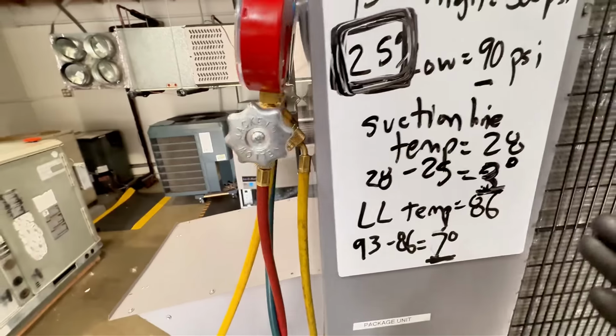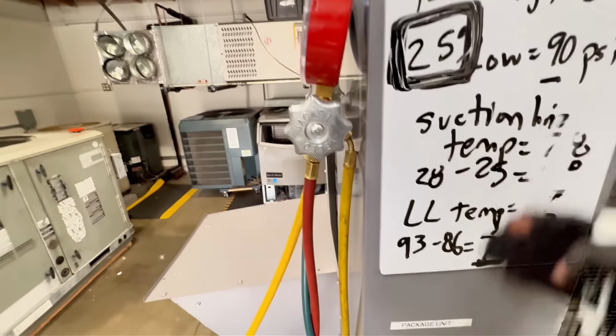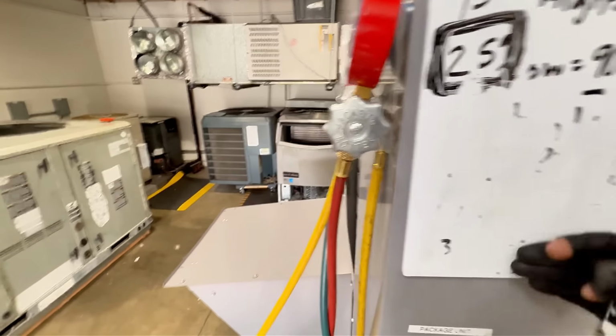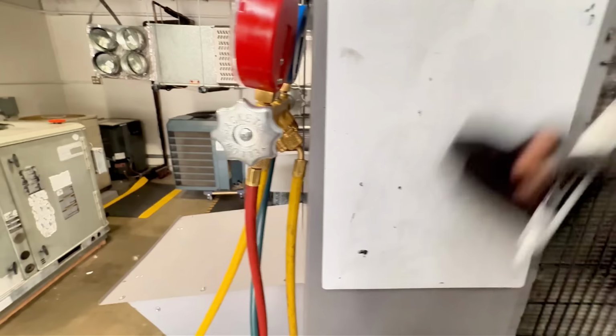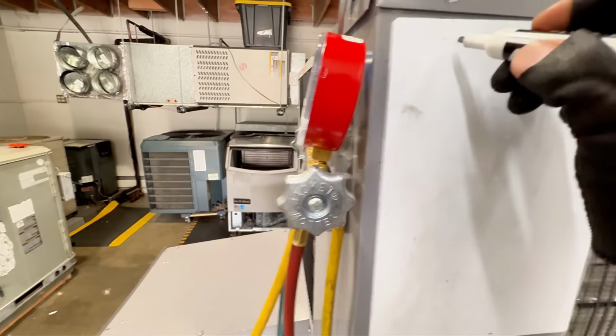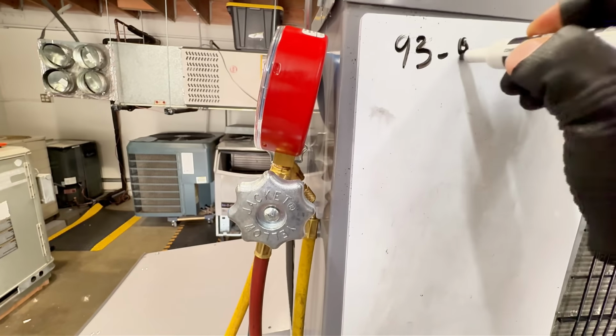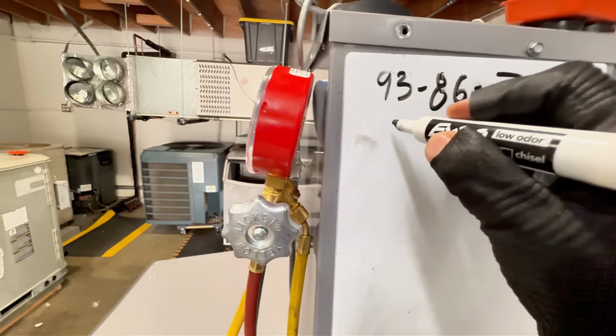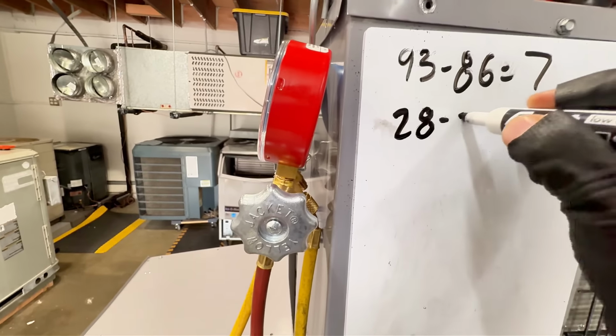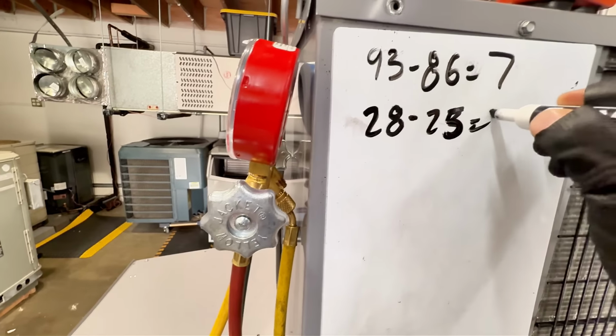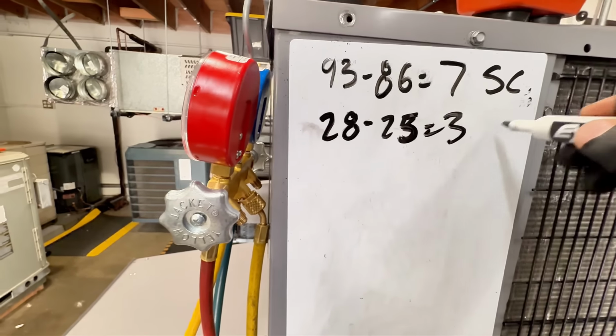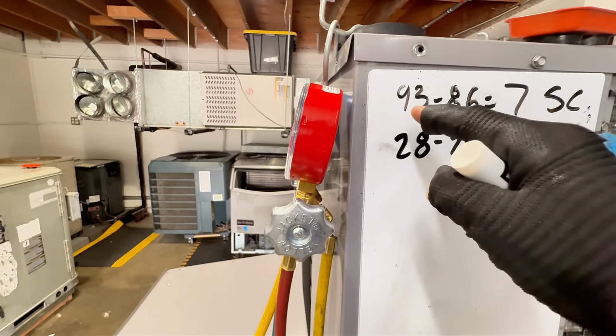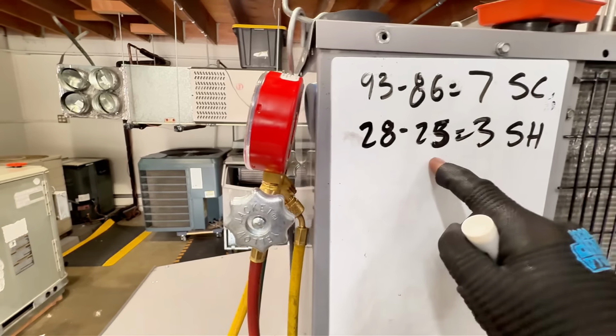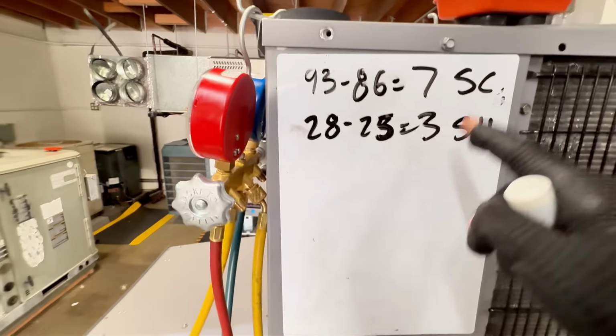So let's do this. I am going to go ahead and erase this so I can make room for the new numbers, because now you have to recalculate everything. That's why you always check airflow first. So what was it? 93 minus 86, 7, and then 28 minus 25, 3. So subcool and then superheat. This one was my condensing temperature. That is my evaporator temperature, right? So those were the numbers.